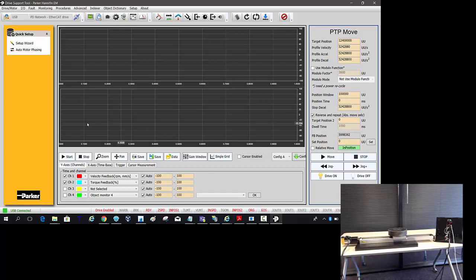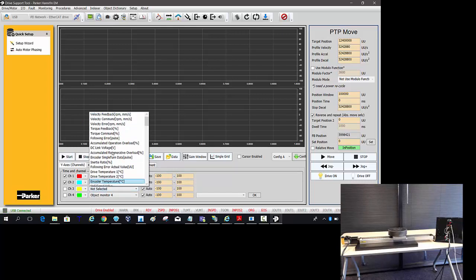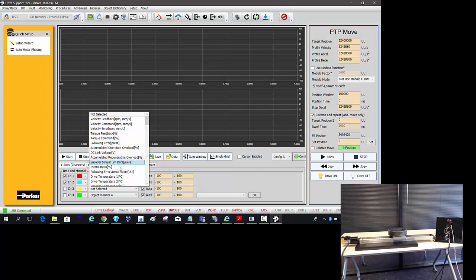So it looks pretty smooth and let's graph this. If we go into the oscilloscope you can see I already have this up. We have the velocity feedback, the torque feedback percentage which is a percentage of the motor that we're using. We want to look at the tracking error, following error, actual value.